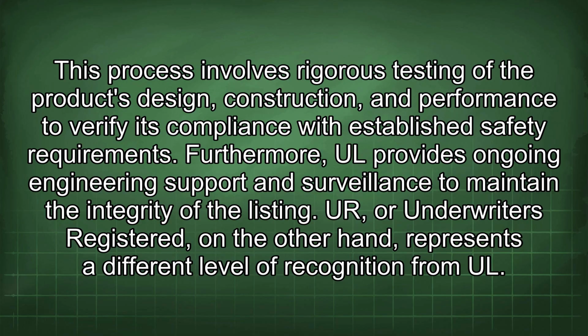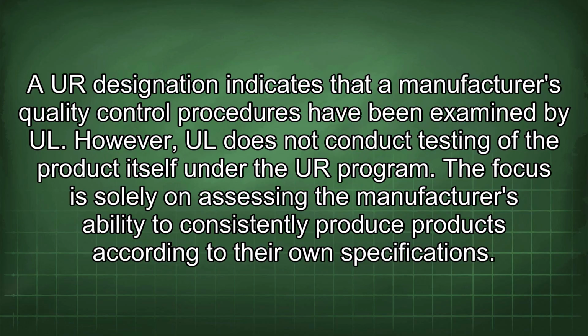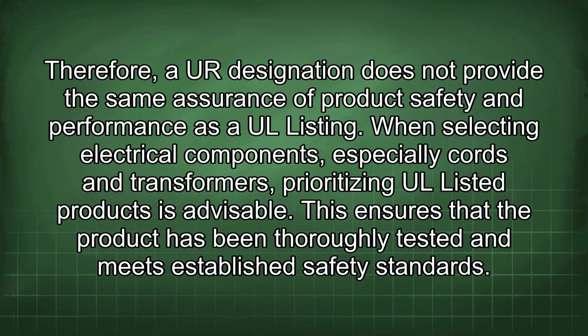UR, or Underwriters Registered, on the other hand, represents a different level of recognition from UL. A UR designation indicates that a manufacturer's quality control procedures have been examined by UL. However, UL does not conduct testing of the product itself under the UR program. The focus is solely on assessing the manufacturer's ability to consistently produce products according to their own specifications. Therefore, a UR designation does not provide the same assurance of product safety and performance as a UL listing.